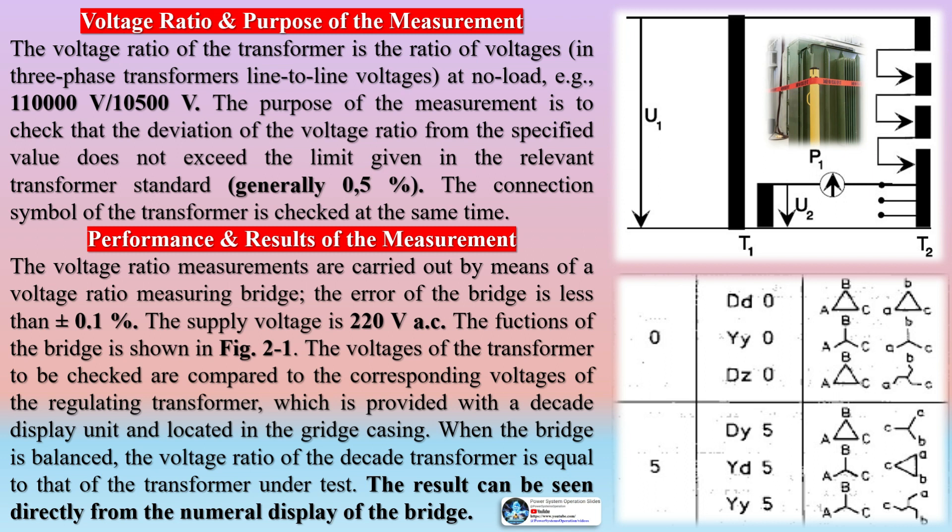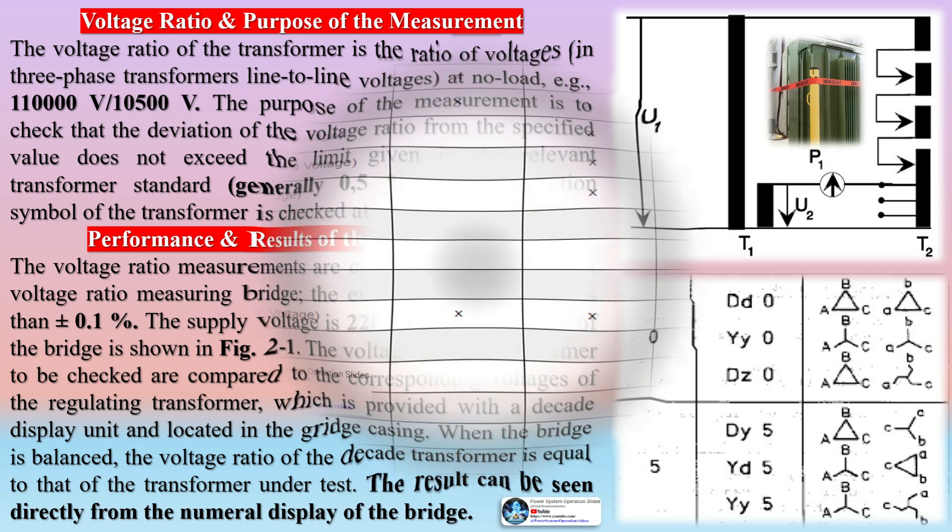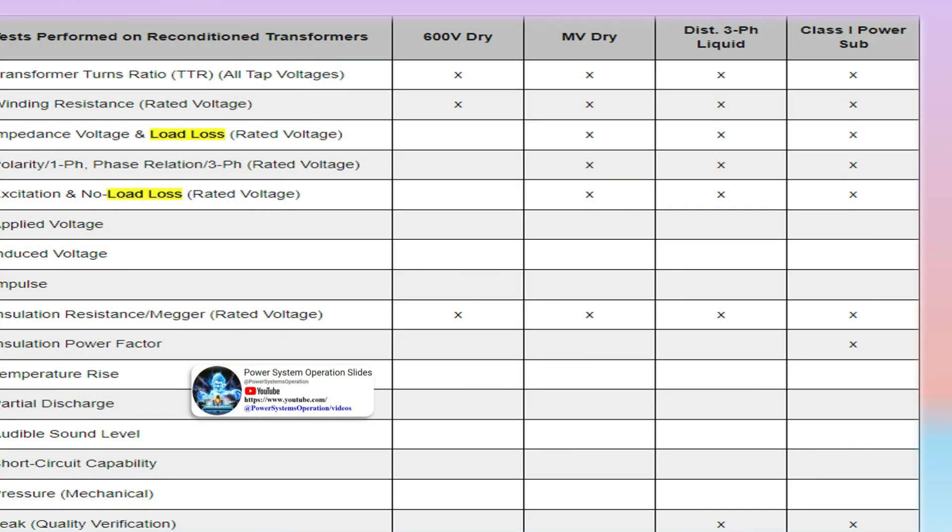Voltage Ratio and Purpose of the Measurement. The voltage ratio of the transformer is the ratio of voltages in three-phase transformers line-to-line voltages at no load, for example, 110,000 V by 10,500 V. The purpose of the measurement is to check that the deviation of the voltage ratio from the specified value does not exceed the limit given in the relevant transformer standard, generally 0.5%. The connection symbol of the transformer is checked at the same time.